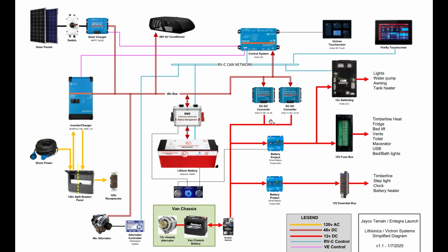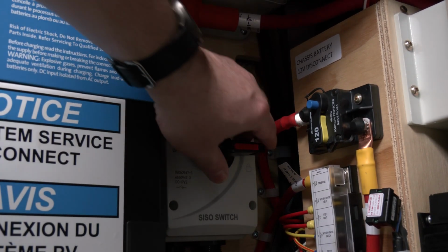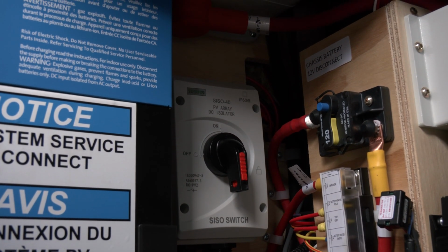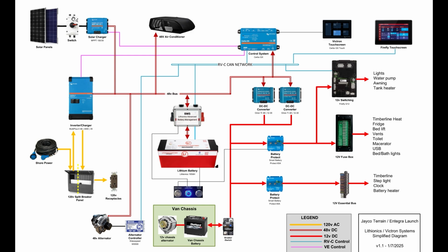One important point on the solar system: you only want to turn this switch on and off when the battery is on, when there's power on that bus. Because if you turn the solar on, or accidentally leave it on and shut off the battery, the solar just doesn't have enough power to power everything on that 48 volt bus. You'll get some beeping and low volt alarms, and you'll know something's wrong — it's likely just that you forgot to turn off the solar switch. So it's best to only operate the switch when the battery is turned on.